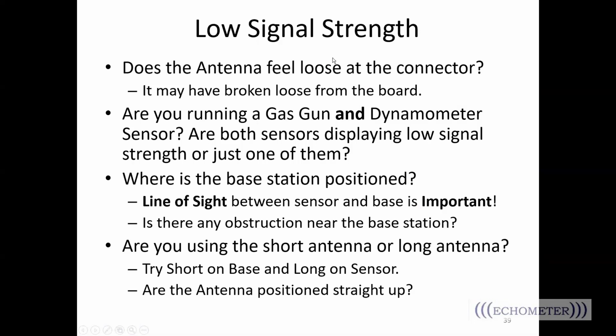Some more troubleshooting as far as the low signal strength. Does the antenna feel loose at the connector? Again, it may have broken loose from the board. Are you running a gas gun and dynamometer sensor? Are both sensors displaying low signal strength or just one of them? So this is where you can kind of start to troubleshoot where your problem is. If you've got a gas gun and a dynamometer and they both are showing low signal strength, then it might be a location problem. If you've got a gas gun and a dynamometer and the dynamometer shows full strength and the gas gun is showing low signal strength, check your antenna. Maybe it's a sensor problem.